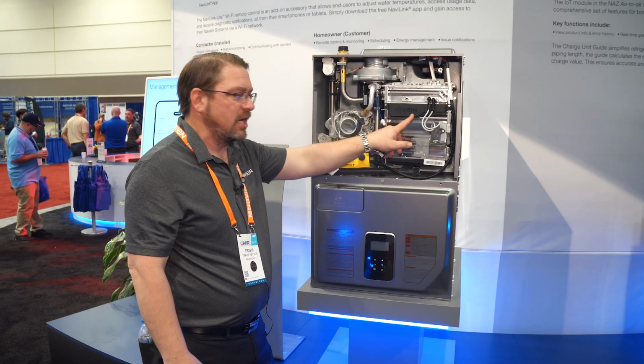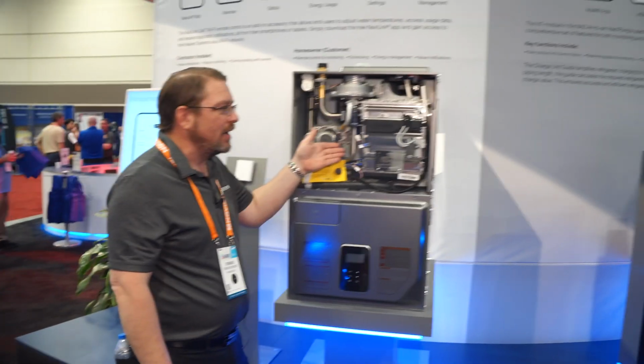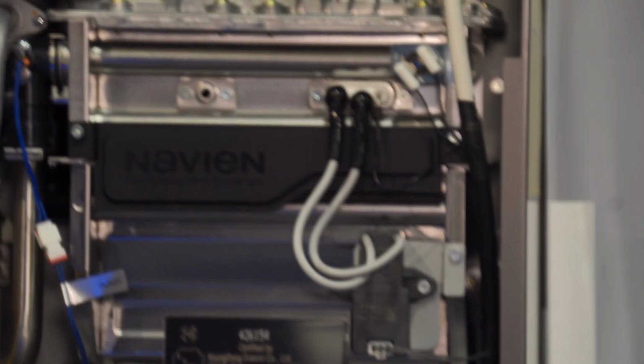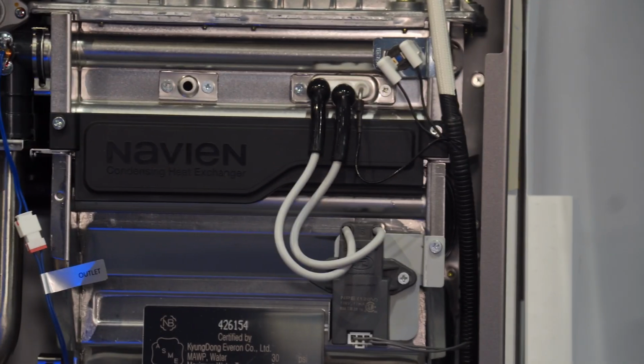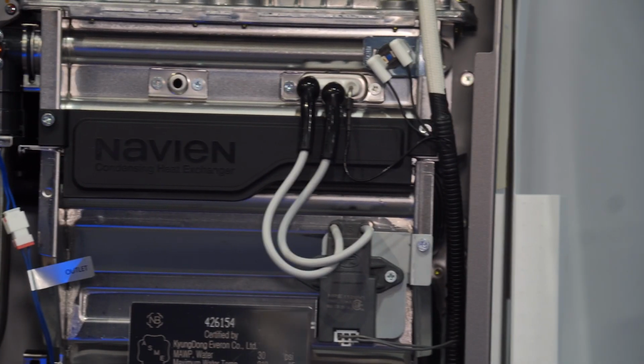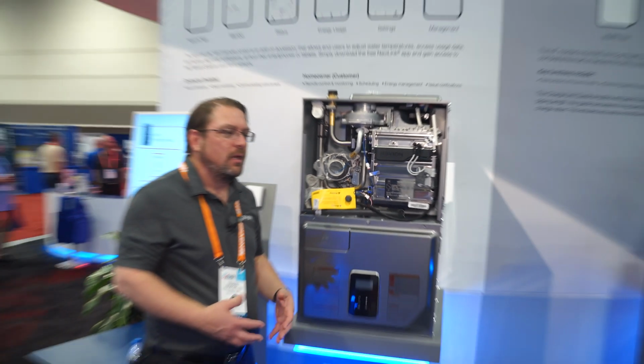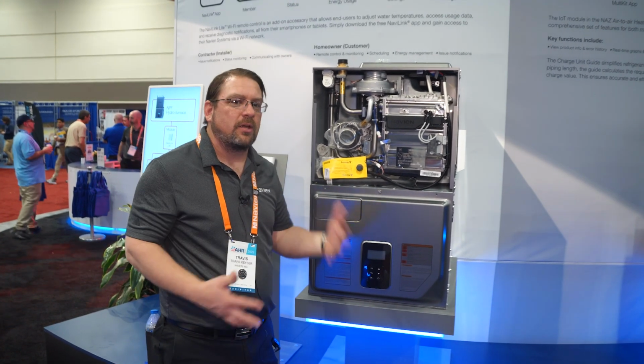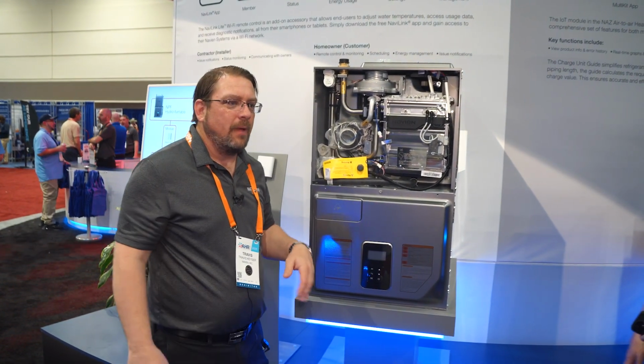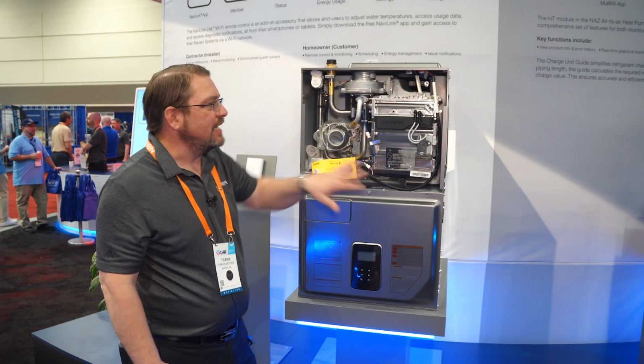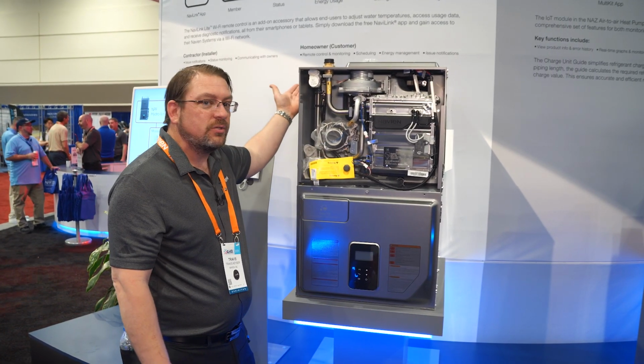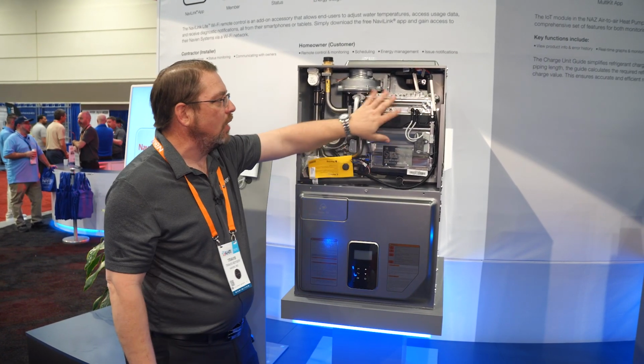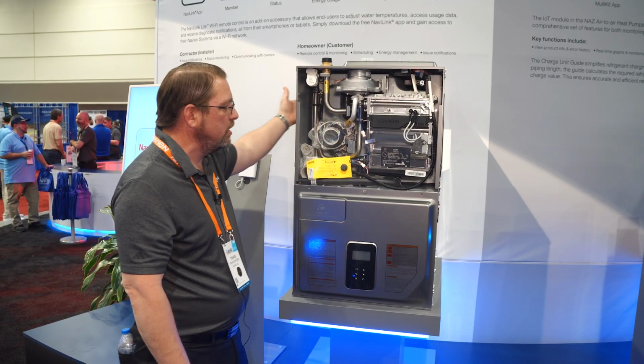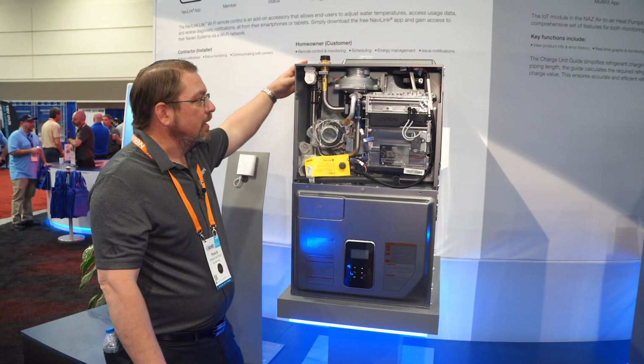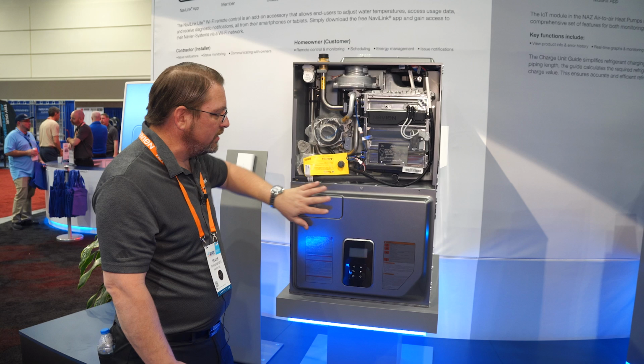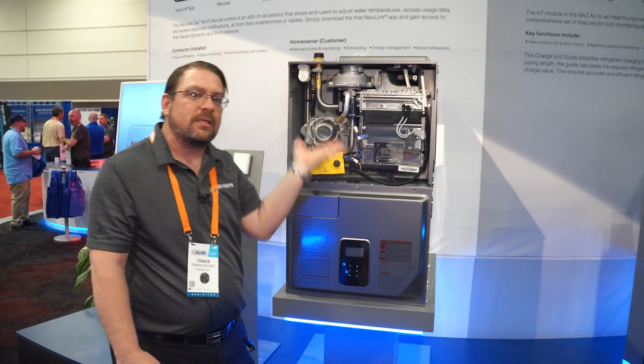This is our heat exchanger. No byproducts of combustion ever enter the airstream, so from a safety standpoint, that's huge. We often hear all of the stuff about failed heat exchangers and carbon monoxide and all of that. None of that is an issue here because none of it ever enters the airstream. Again, we're heating the water, it goes into the hydronic coil, warms the air, that cooled water comes back down into the reservoir and then gets recycled again.